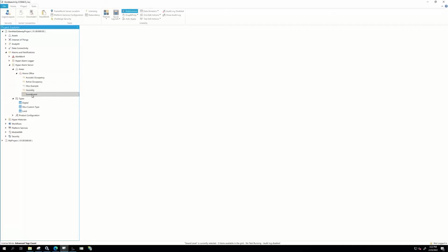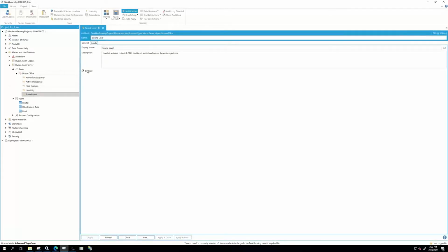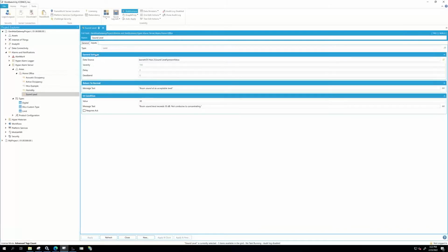For example, I've created an alarm on sound, and I just call it something. The input I've done is I've taken the BACnet data point I showed you earlier, and said if the sound is over 30 decibels, display this alarm. If it's not, go back to saying this is fine.